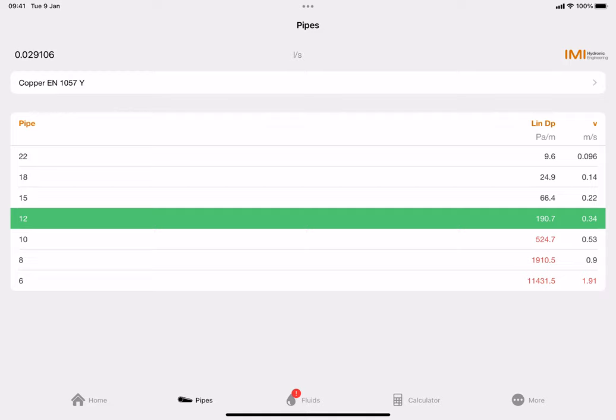You need to work out what an index circuit is of a heating system in order to size a pump correctly. As long as you get over the index circuit of any system - it doesn't matter if it's a one-bedroom flat or a thousand-bedroom hotel - it makes absolutely no difference. The index circuit could be a pipe run, a radiator, an emitter, a flow and return, a manifold, or a valve - whatever has got the most resistance.